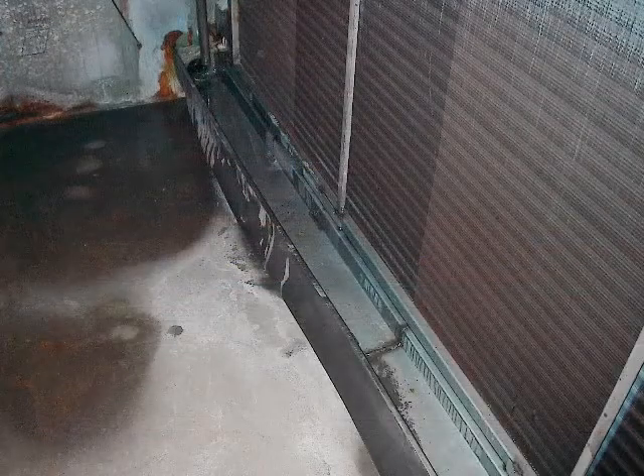Take a look at these coils. This was a refurbished unit. It had been in operation at the time of this picture approximately 7 to 8 years. And take a look at the coils. These are perfect operating conditions, no debris, no food source. And as a result of these clean conditions, this system is operating at peak performance at all times. So they're conserving energy, they're providing the best indoor air quality possible, and most importantly, there's no food source for microbial growth.